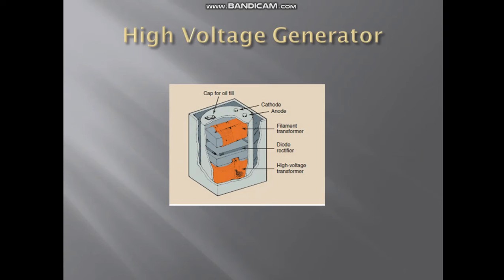And lastly, we have the high voltage generator, which is responsible for increasing the voltage output from the autotransformer necessary for X-ray production. If we look inside the high voltage generator, we can see that it has three main components: the high voltage transformer, filament transformer, and the diode rectifier.